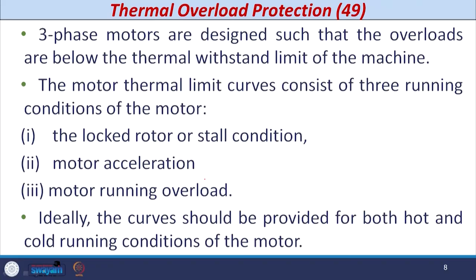Three-phase motors are designed such that overloads are just below the specified withstand value of the motor. The motor thermal limit curve consists of three running conditions: the first is the locked rotor or standstill or stall condition, the second is the motor in acceleration condition, and the third is the motor running with overload condition. Ideally, all three curves should be provided for both hot and cold running of the motor.